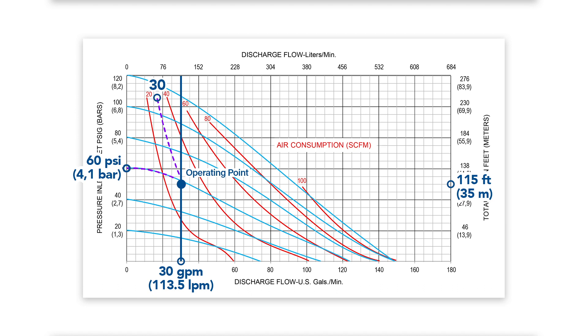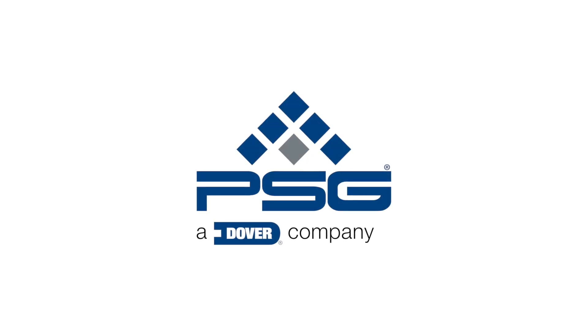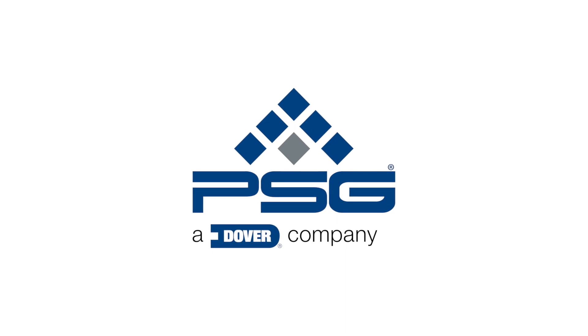Generally, whether pumping a liquid similar to water or something much more viscous, it is recommended to always operate an AODD pump in the middle part of its performance curve, rather than at the extreme conditions. This is the most efficient way to operate an AODD pump, not only from a performance and air consumption perspective, but it also helps extend the life of wear parts.